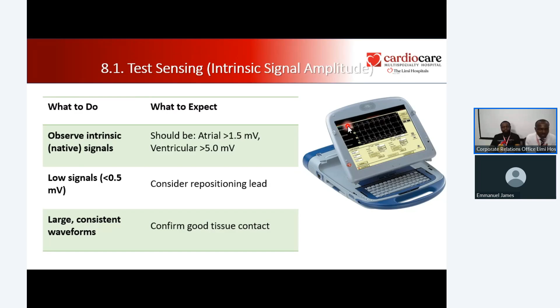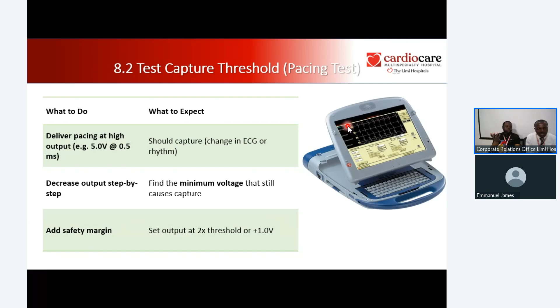And then once we are done with the sensing, there's sensing and there's pacing. Remember the VVI. So the pacing part is all about the capture, because we want it to be able to stimulate the heart. If it cannot achieve that with as little as less than 1 volt, then we have not really gotten a good placement. So we want to ensure that we can deliver pacing with a very low voltage. If I use a high voltage to deliver pacing, the battery will run down. We also check the impedance.